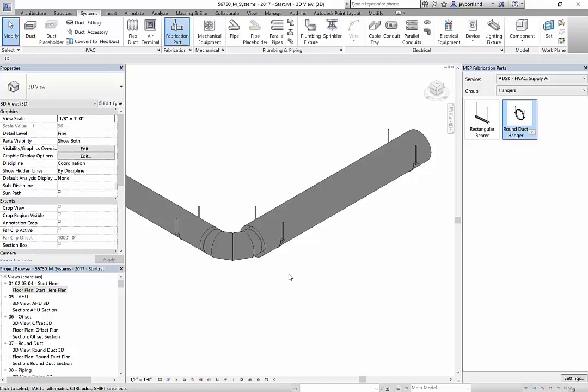So it's a 2-inch thermal lagging, and it's going all the way around, so it's actually upsizing that hanger by 4 inches, right? Because there's two sides to that 2-inch lagging. So it went from a 14-inch diameter hanger to an 18-inch diameter hanger.